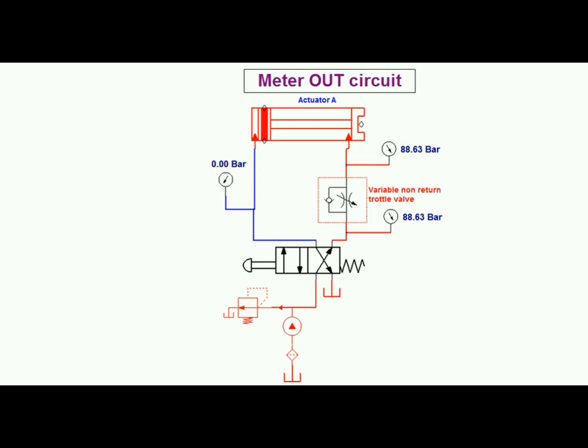It is the opposite of a meter in circuit operation as this change in direction will cause the fluid leaving the actuator to be metered. The advantage with the meter out operation is that unlike in the case of meter in circuit operation, the cylinder here is prevented from overrunning and consequent cavitating.